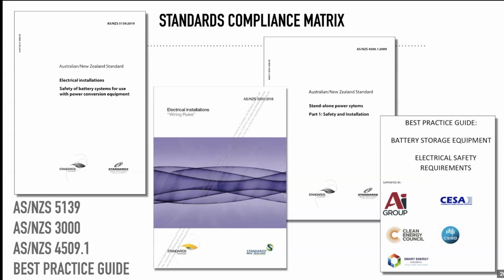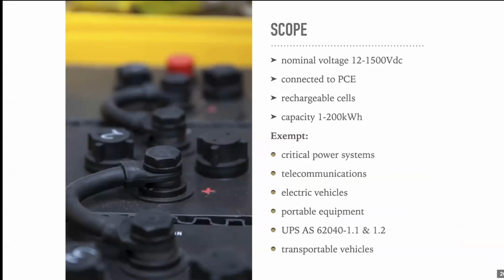We're going to look at the scope of 5139. Now, if you're not familiar with how standards work in Australia and New Zealand, the first thing you should always do is read the scope to make sure it even applies to what you're doing. I remember when this standard was in draft, a lot of people were concerned that it would be impossible to put a battery in a caravan, because one of the things the draft said is that you shall not put a battery in a habitable room, and there's nowhere that's not habitable in a caravan. But it turns out it's actually exempt.